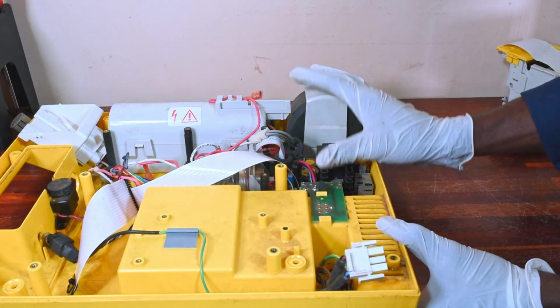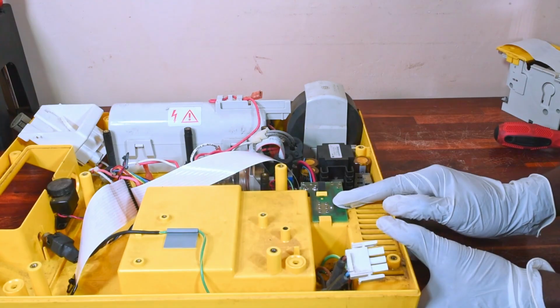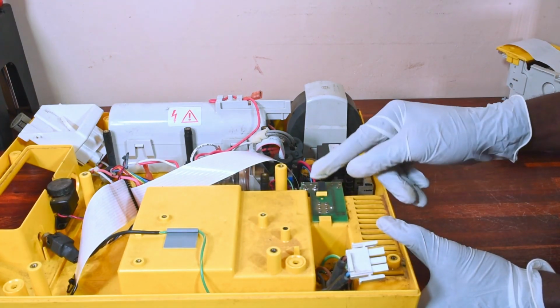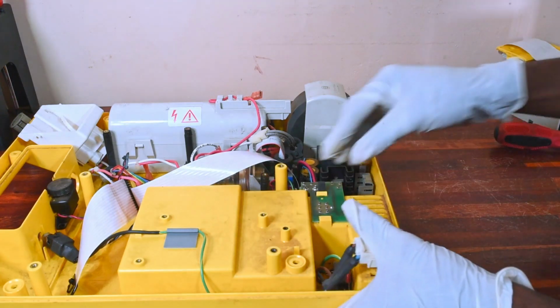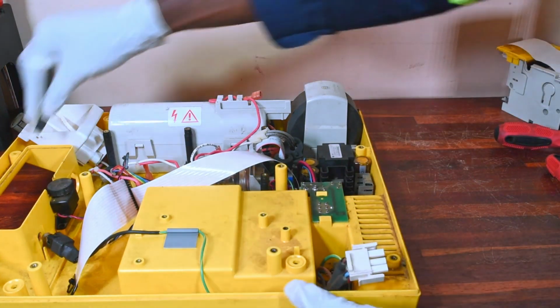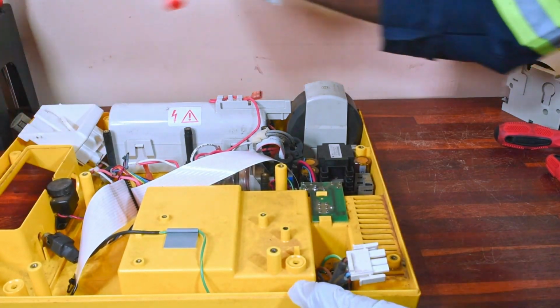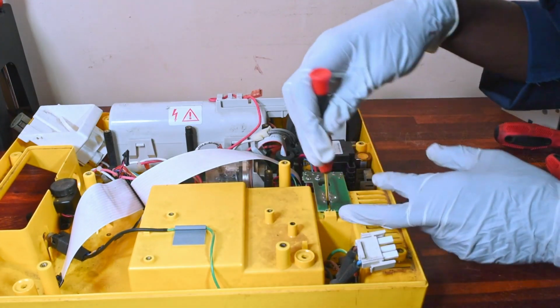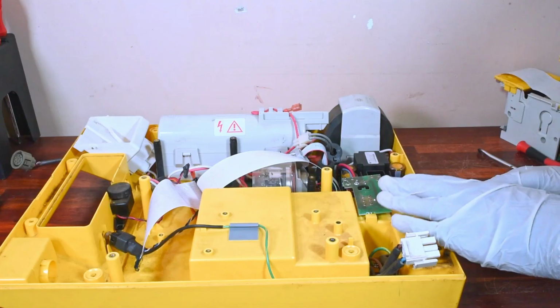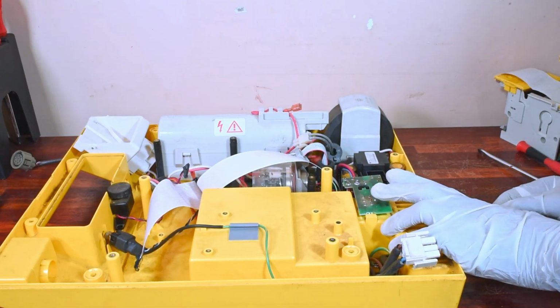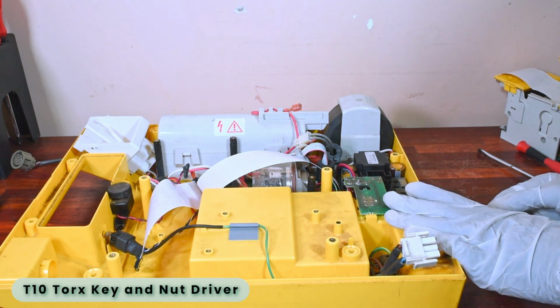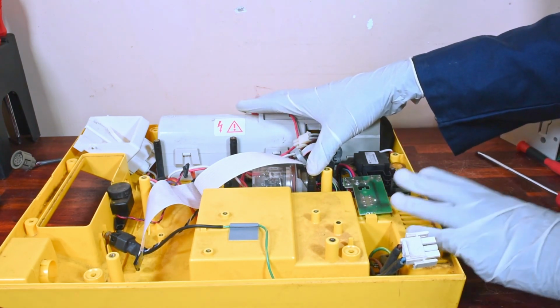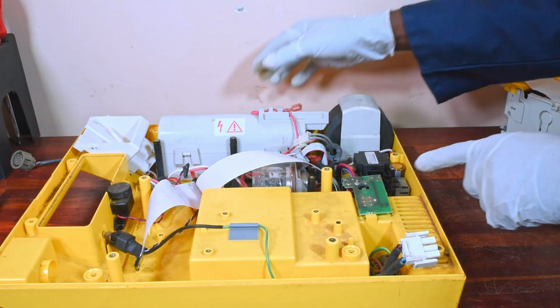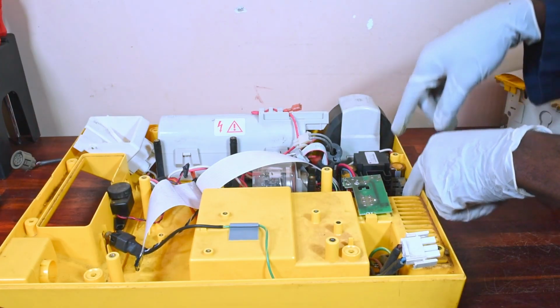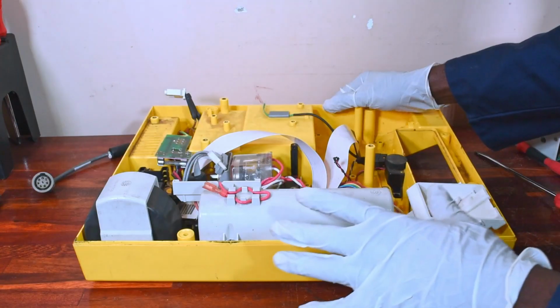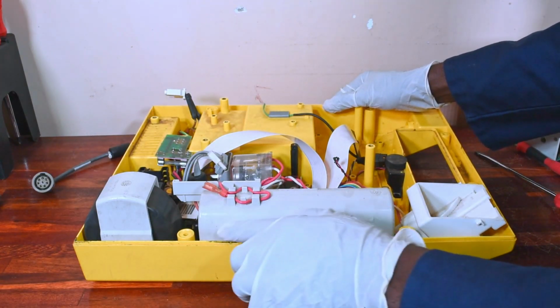To remove this assembly, start by disconnecting the battery connector board by removing this black rubber and releasing the locking latch securing the board in place. After disconnecting the battery connector, I will use a T10 Torx key and a nut driver to remove the screws fastening the assembly to the chassis. 2 of these screws are located on the high voltage control board, and the other 2 are located on the high voltage capacitor case.